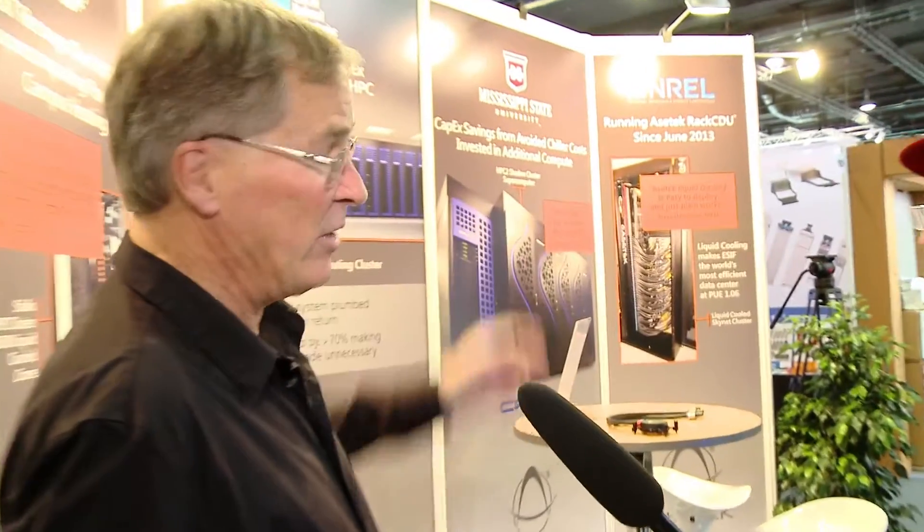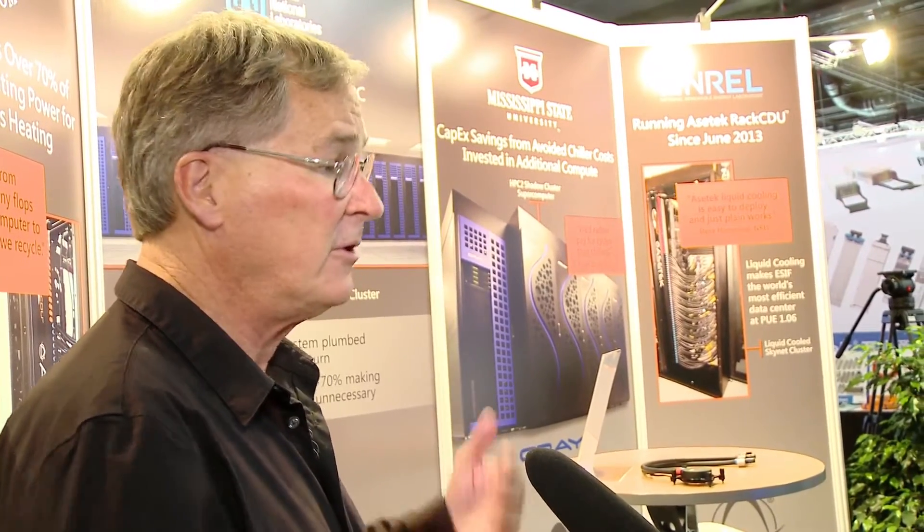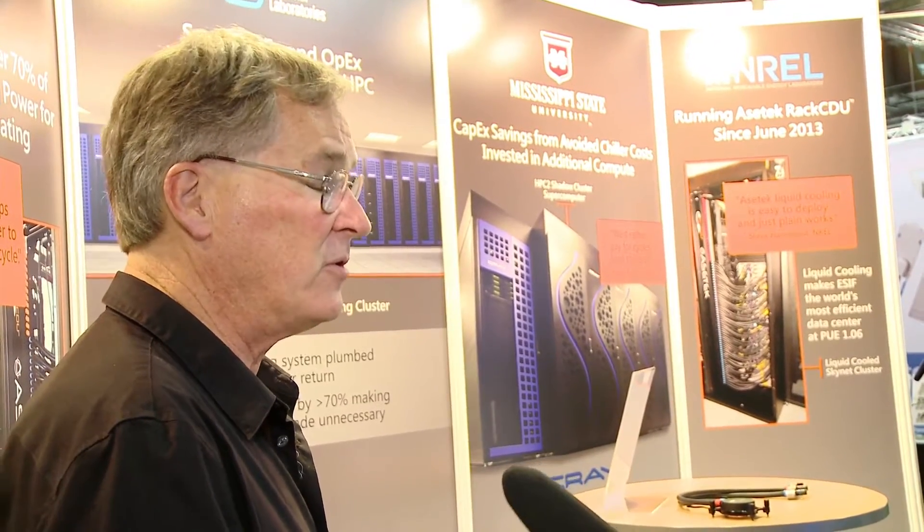NREL, which is our oldest deployment, has now begun to add additional small systems to their data center, and they've purchased additional liquid cooling systems for that data center. That is, of course, the ESIF data center, which is operating at a PUE of 1.06, and they're doing that by having an all-liquid-cooled data center. So we're supporting that infrastructure as we build out.